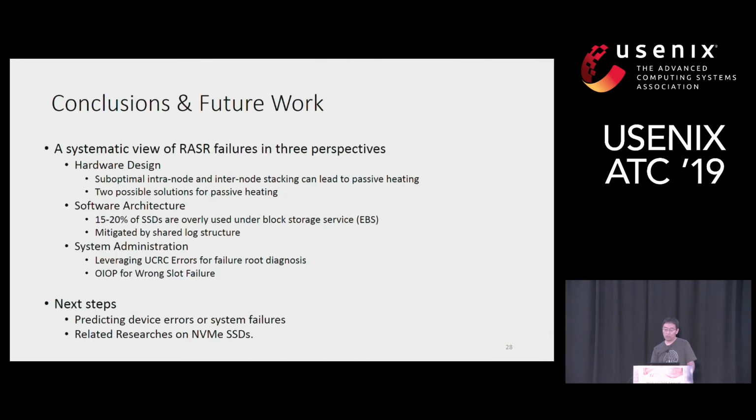And for conclusions, we looked at about 10,000 SSD-related failures in our system over 3 years. And we evaluated them from 3 angles: hardware, service design, and administrative point of view. The first conclusion is that passive heating in the data center is real, because SSDs are less temperature tolerant, and they are considered a hot tier, and they stay close to CPUs and other SSDs.